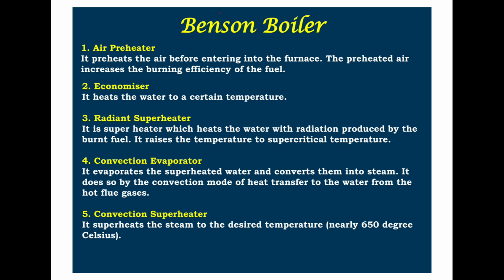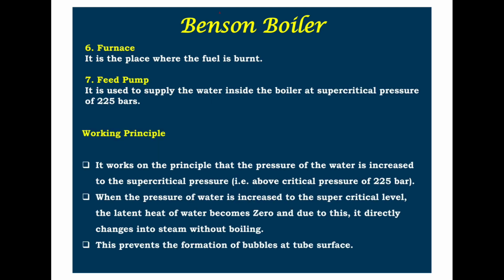superheats the steam to the desired temperature, nearly 650 degrees Celsius. And the Benson boiler furnace is the place where the fuel is burned, and the feed pump is used to supply the water inside the boiler at a supercritical pressure of 225 bar.